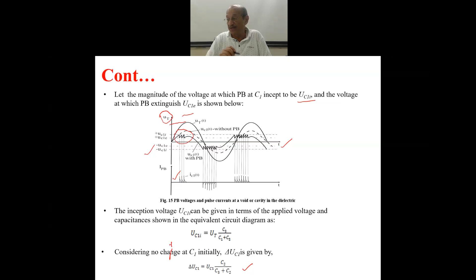can be estimated to be the UC1, the voltage applied at the weak point C1, times C2 upon C3 plus C2, from the equivalent circuit. That means delta UC1 is equal to the voltage across the weak point UC1 times C2 by C3 plus C2. And if the voltage drop at C1 is assumed to be equal to the corresponding drop in applied voltage at the test object, delta T, I mean the corresponding drop in the applied voltage, because the drop due to the breakdown process at the weak point is taking place, then the corresponding drop at the terminal, delta T, can be given as UT times C2. From this equation you can derive C2 square upon C3 plus C2 into C1 plus C2.